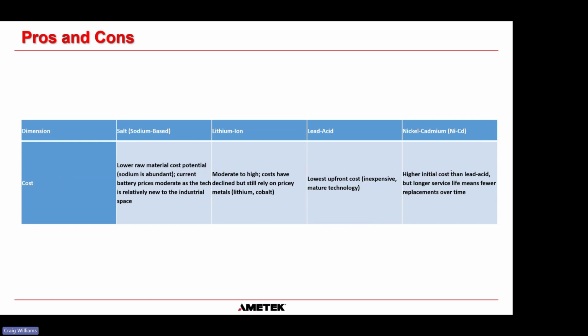And then NiCads, a much higher initial cost than lead acid, but they have a longer service life, allegedly. Which means fewer replacements over time. You have to weigh that up, okay? And in truth, I think that's comparing it to valve-regulated lead acids. Wet cell or vented lead acid batteries tend to have the same lifespan as a NiCad battery.